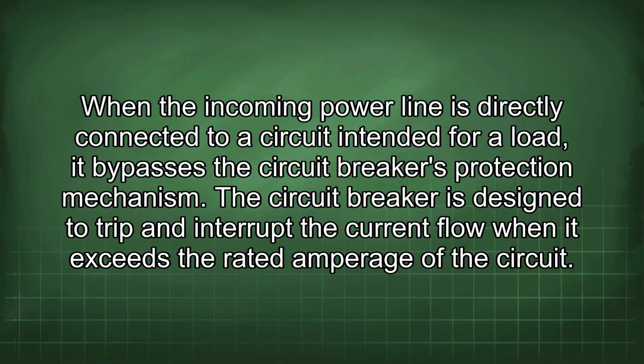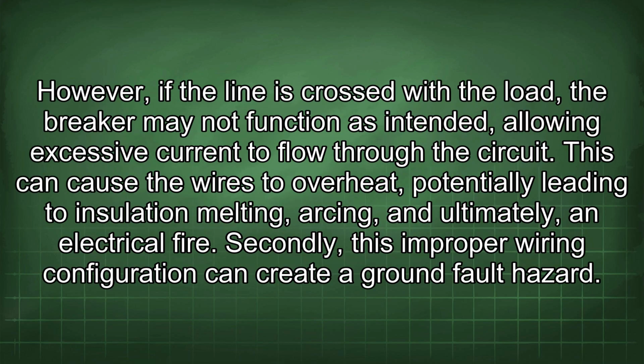When the incoming power line is directly connected to a circuit intended for a load, it bypasses the circuit breaker's protection mechanism. The circuit breaker is designed to trip and interrupt the current flow when it exceeds the rated amperage of the circuit. However, if the line is crossed with the load, the breaker may not function as intended, allowing excessive current to flow through the circuit. This can cause the wires to overheat, potentially leading to insulation melting, arcing, and ultimately, an electrical fire.